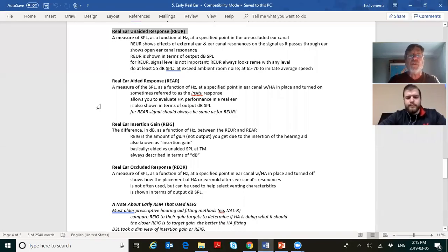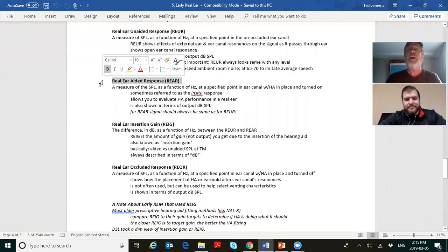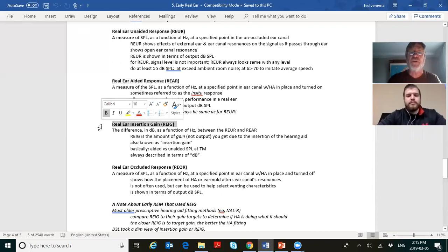Unaided ear canal response. Open unaided ear canal. Do it at about 55 dB SPL to exceed ambient room noise. Good English there, Ted. All right. Then real ear aided response. Then real ear insertion gain, which is the difference.